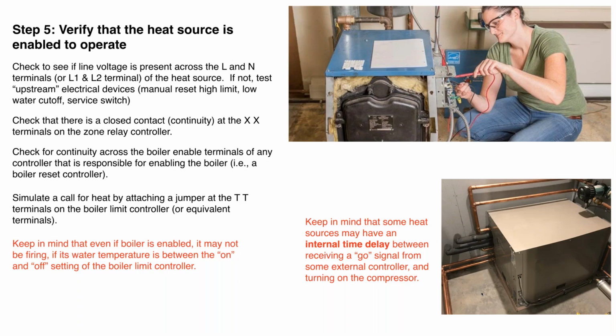Those are built-in time delays, and they're in there to prevent a short cycling problem where a compressor's been on, it shuts off, and then 5 seconds later, it attempts to restart against a high refrigerant pressure. So again, keep that in mind, look at the documentation, make sure that you understand if there's a time delay function built in.